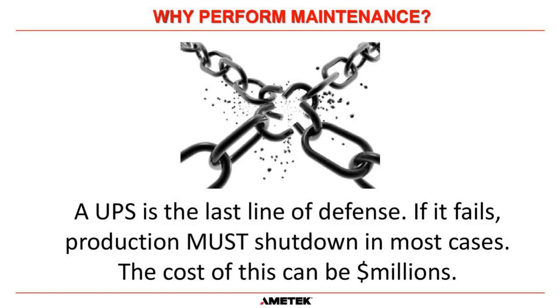An example of that is, say it's a 24-hour, 365-day-a-year plastics plant, and they're extruding plastic through their extruding machines, and the plastic is being made at the plant. If the production stops and the flow of the plastic stops through the pipes, that plastic goes hard and it plugs. And in some cases, you've got to go out and you've got to cut pipes, weld pipes, and the plant could be down for maybe 24, 48 hours. And that is a huge cost hit. And it could be a huge safety hit as well because of all the other work that is caused by it. So that is why it's important to keep your UPSs up and running as much as possible.